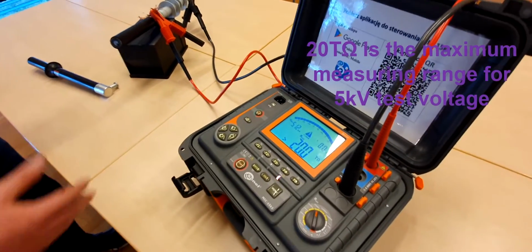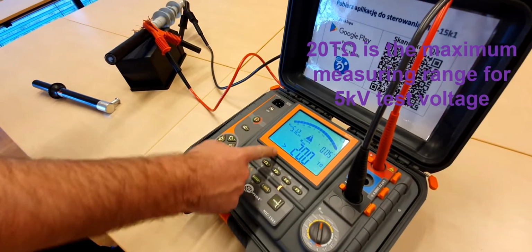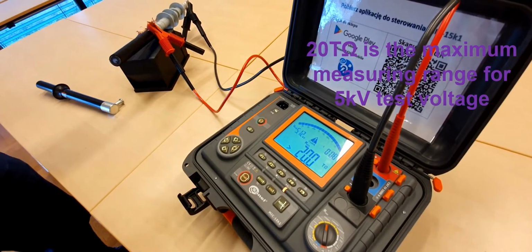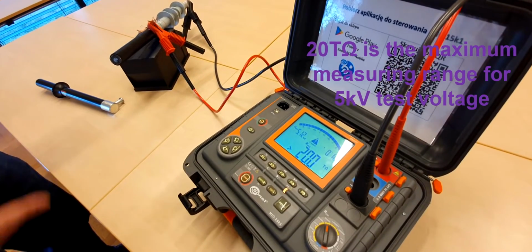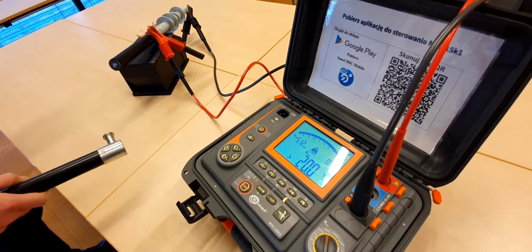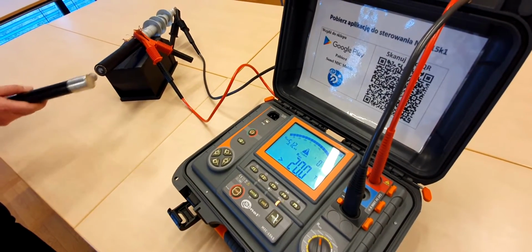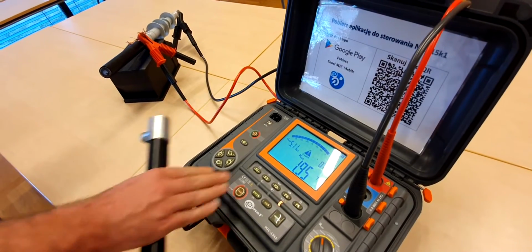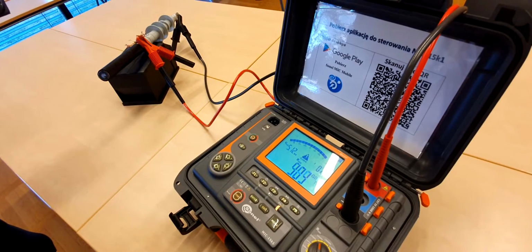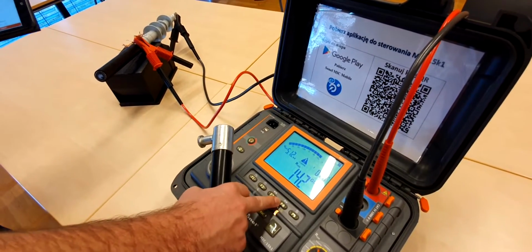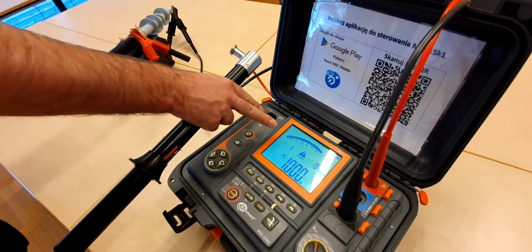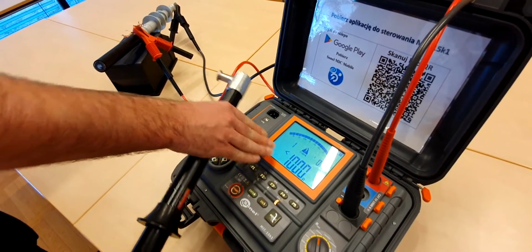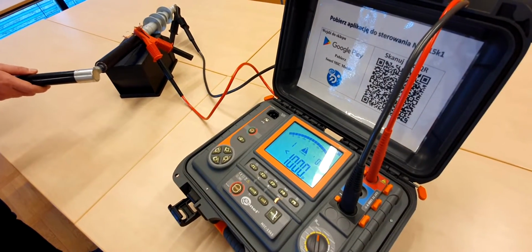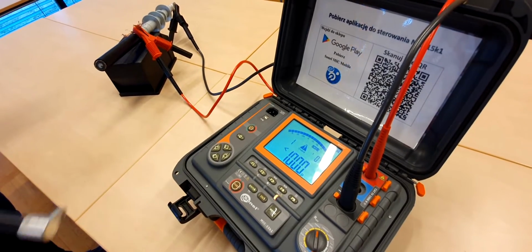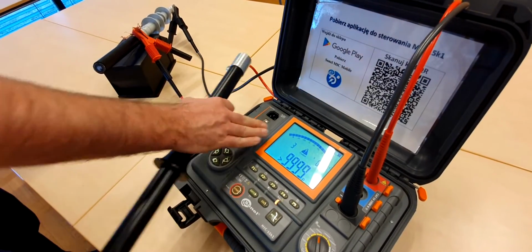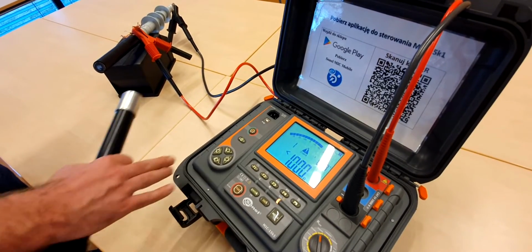And as we are measuring our cable, we can see that the numerical value of the resistance of insulation is quite high. But what happens when I simulate some partial discharges? So let's simulate them. Well, we can see a fluctuation in the numerical value of the resistance of the insulation. But once I press the F4 button, we will be able to see the number of partial discharges per second and their numerical value. So we were able to see that there were about 14 partial discharges per second and their value.